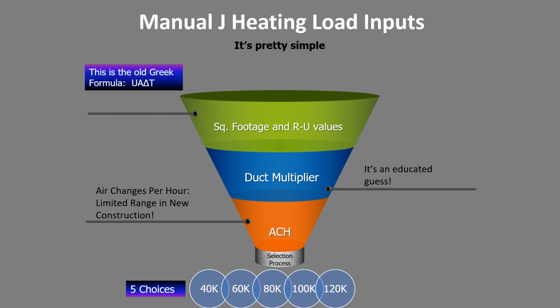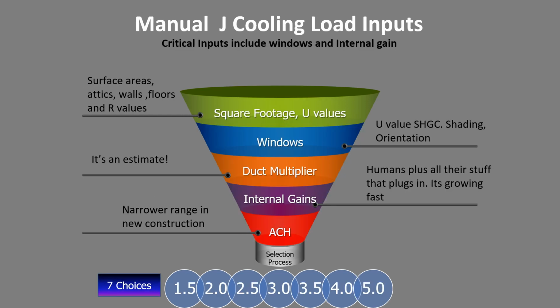So when it comes to doing a heating load or a cooling load, it's sort of that old Greek formula. You need the square footage, the R and U values, you need the duct multiplier, and quite honestly, the duct multiplier is a bit of a guess. We'll give you some guidance on how to pick it. And ACH, or how leaky or tight the house is, ACH standing for air changes per hour. We go through the selection process, and when you're putting a furnace in, they come in big BTU increments: 40, 60, 80, 100, and so on. We don't have to be super precise. There's an old saying in the heat loss business: horseshoes, hand grenades, and heat loss. Close really does count.